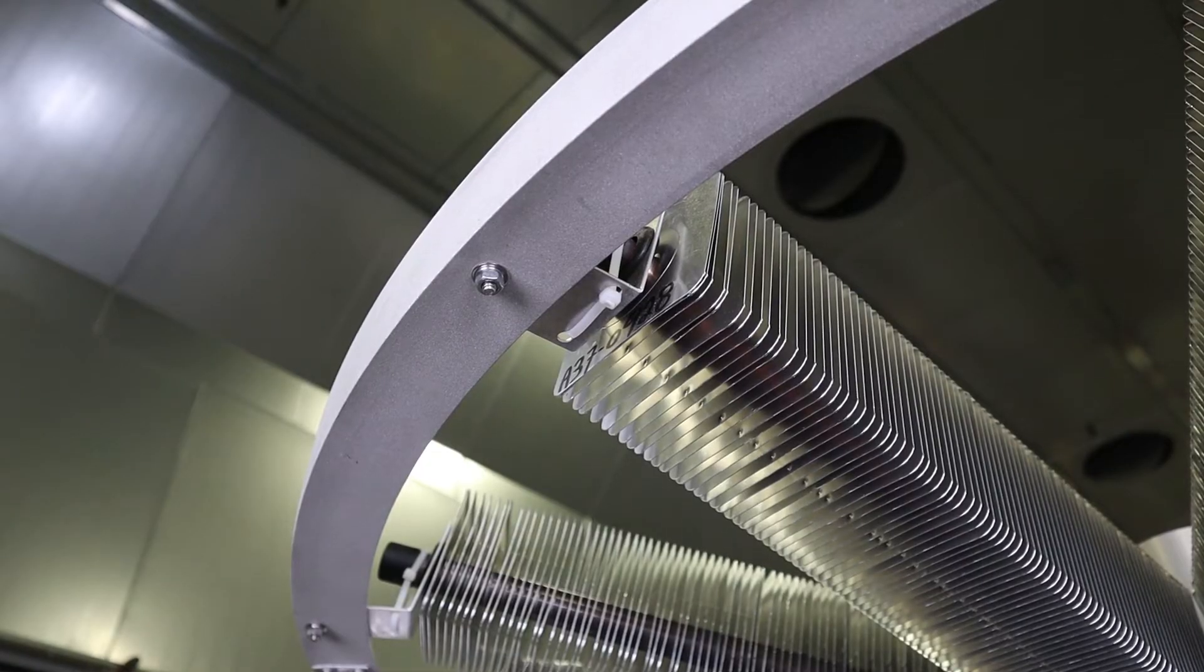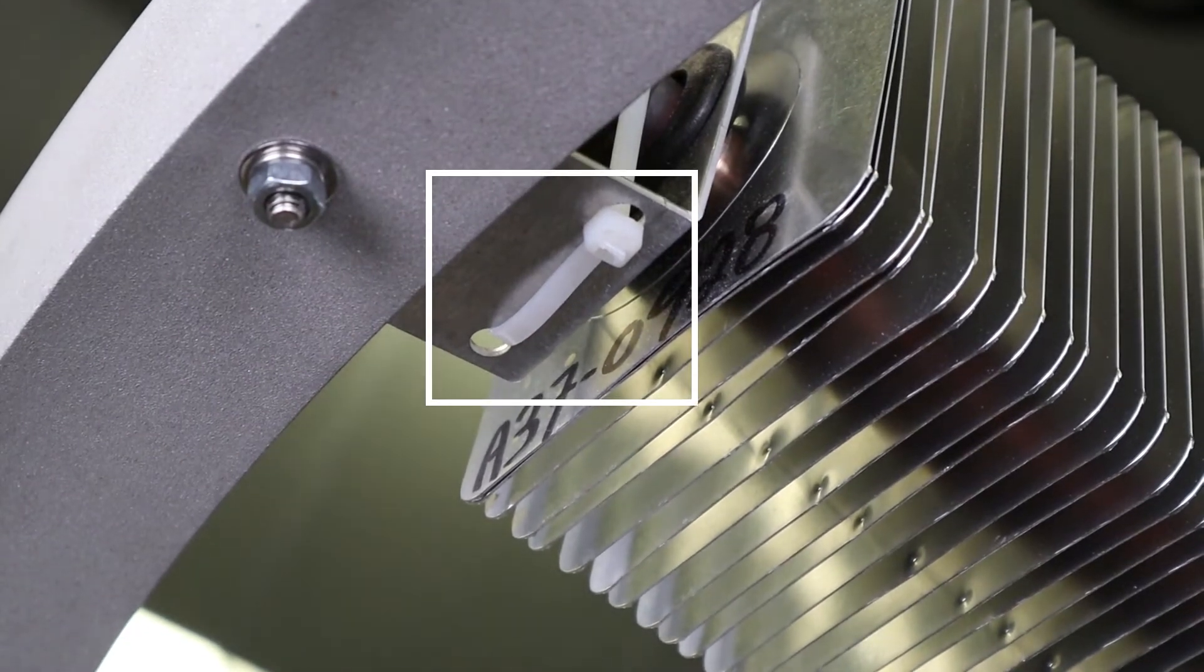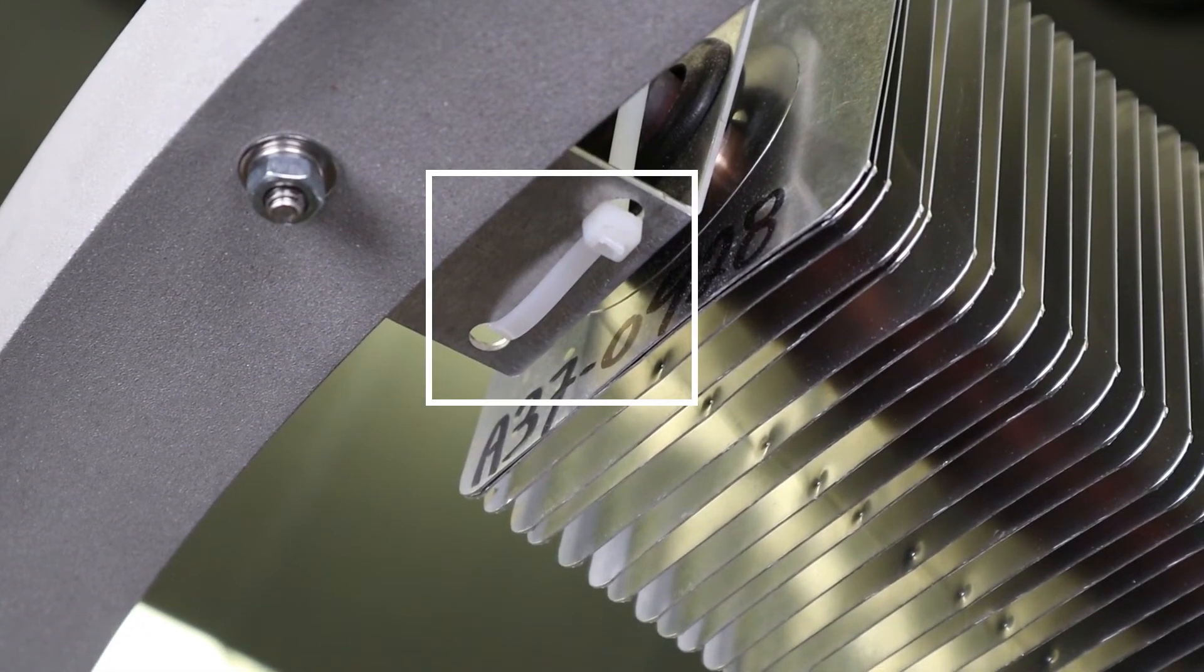Lastly, we're going to remove the tie wraps that clamp the ends of the heat pipe to the support ring. Failure to do this could cause the heat pipes to crack when they expand.